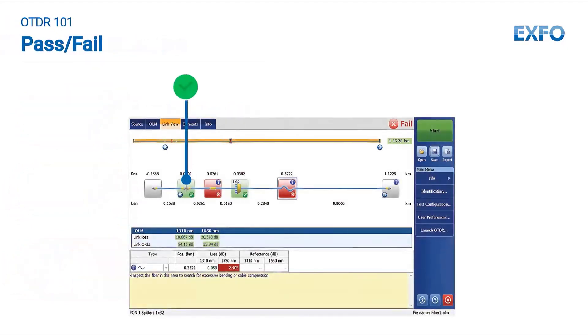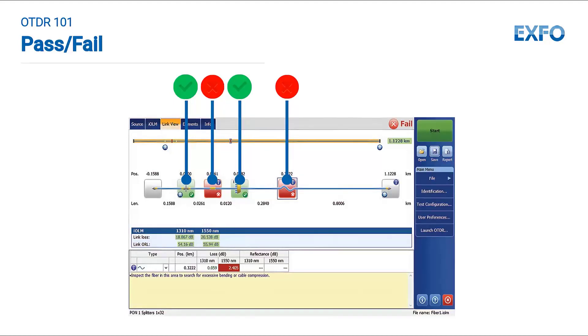Link elements: each event — connector, splice, etc. — needs to respect its individual loss level and reflectance as applicable. Even if the total link loss budget is respected, an event that exceeds its individual tolerances is a weakness in the link for future upgrades and a failure risk.